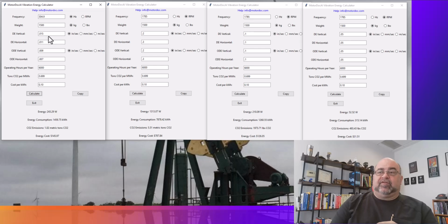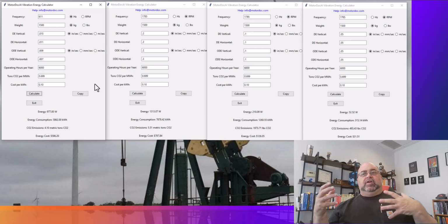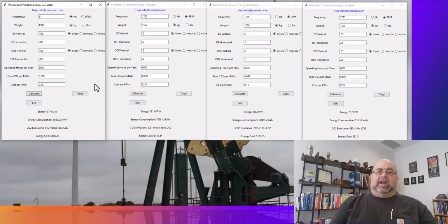So if I have several peaks at that, take the average frequency associated with it. Say I'm at the second harmonic. So that would be 304, 304 would be 610. So let's say 611 hertz. Say I'm only seeing the second harmonic at that. I calculate it, then that gives me a higher number, and so on. So as my problem gets worse, as other things go on, I can start calculating those peaks. But right now, I can only do it by a frequency.